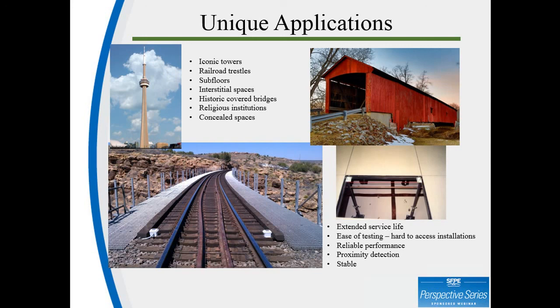Linear heat can be found below subfloors, in concealed spaces, and within interstitial spacing, or basically the areas above a drop ceiling, because it provides continuous coverage anywhere along its length. It also makes complying with NFPA testing requirements very convenient, as you only have to access the end-of-the-line resistor and short the detector. The detector is employed in these unique applications for many of the same reasons that it's used in other places, whether it's the extended service life, reliable performance, ability to offer proximity detection, and the fact that complying with NFPA testing requirements is easy.